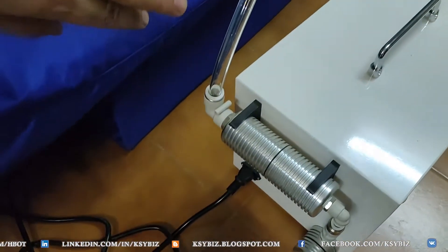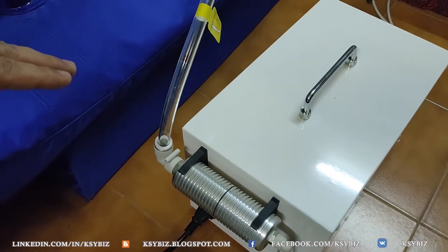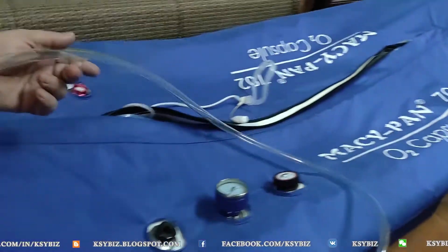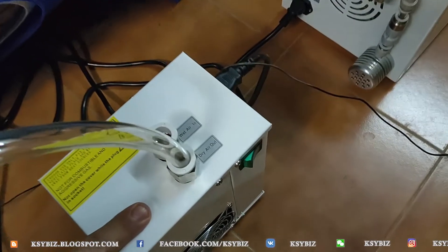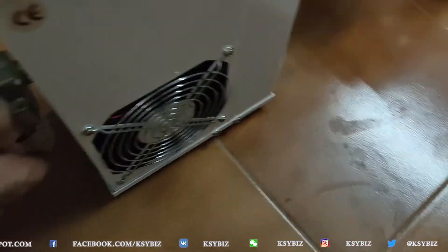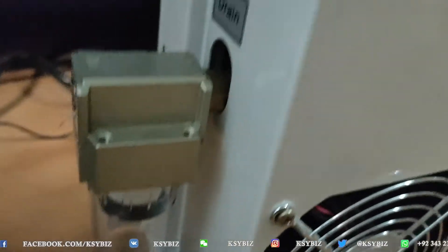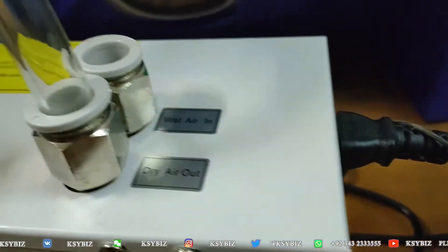Here is the compressor. This compresses the air which goes into the hyperbaric chamber. This transparent pipe goes into one of these two valves on top of the dehumidifier. This is the dehumidifier — it has a fan here, an on-off switch here, and a bottle for collection of water. On top, there are two valves: one is the in valve and one is the out valve. The in valve is the wet air.